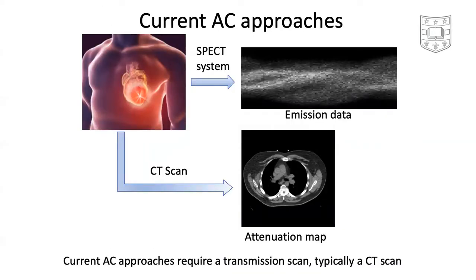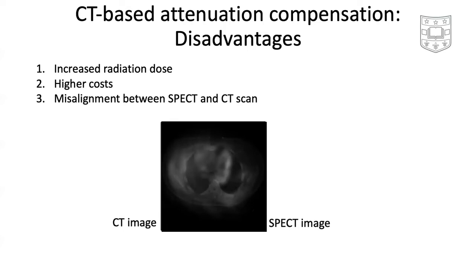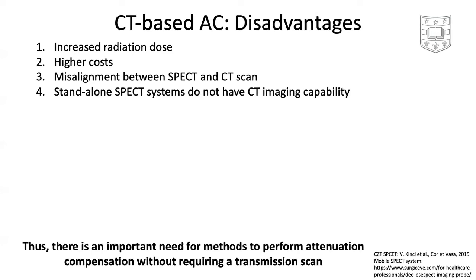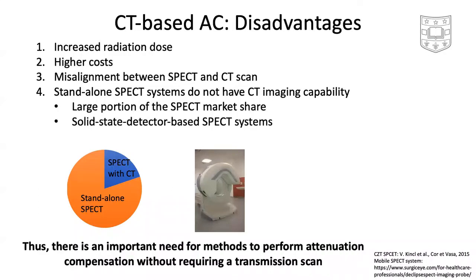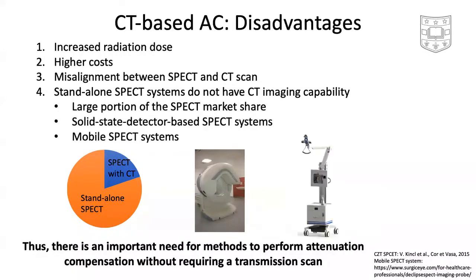Performing attenuation compensation requires the availability of an attenuation map of the patient. This attenuation map is typically obtained by doing a transmission scan, typically a CT scan. This CT-based attenuation compensation method suffers from several disadvantages, including increased radiation dose and higher costs. Further, misalignment between SPECT and CT scans can occur, which leads to inaccurate attenuation compensation. Typically, the CT scan is obtained with a SPECT/CT system. However, a large portion of SPECT's market share is occupied by standalone SPECT systems where a transmission scan is unavailable. Moreover, several emerging solid-state detector-based SPECTs, as well as mobile SPECT systems, do not have CT imaging capabilities.